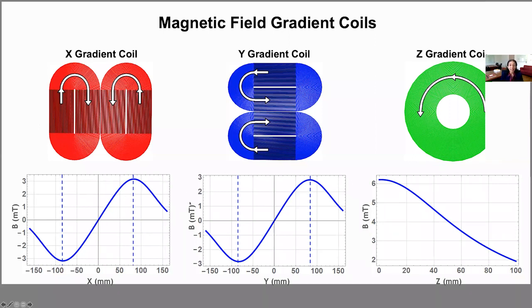So we generate X, Y, Z magnetic fields with almost linear gradient in a relatively large field of view in the XYZ directions by having 3 sets of coils, as I'm showing. The first, the red one, creates the gradient in the X direction, the blue one creates the gradient in Y, and Z creates the Z. A lot of simulation and engineering went into designing these coils to generate reliable and very well-known gradients in these magnetic fields.